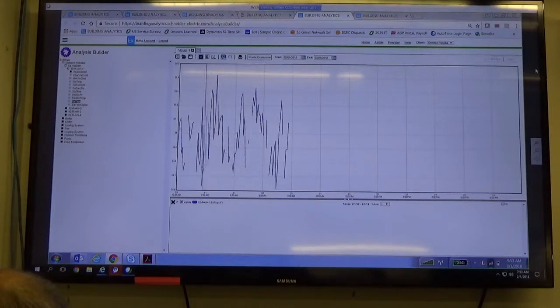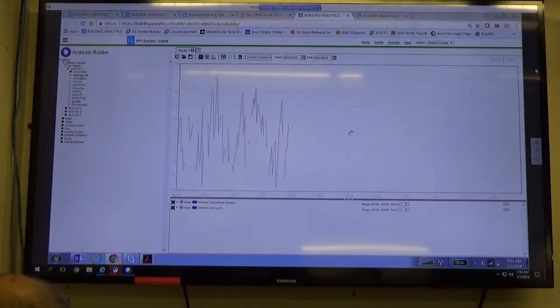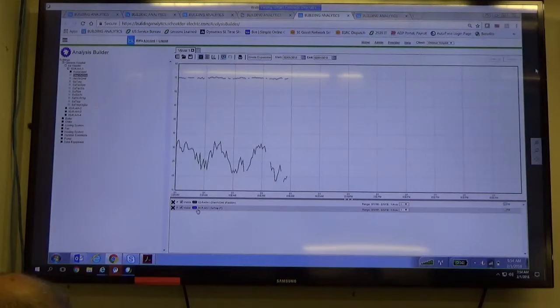But you can look at the supply temp and hover over any given time. At 6 a.m. it was 54.99 degrees. And maybe you want to compare that to what your chill water valve is doing at the time. The supply temp down here is in purple. You can see there's supply temp, and it'll show you the unit name and point if you hover over it. Down here in green is a chill water valve command.